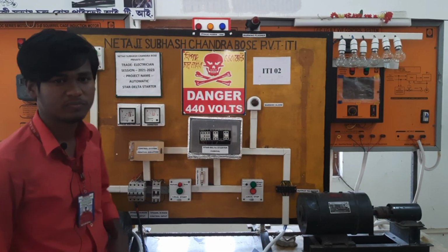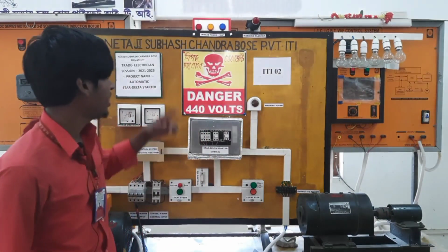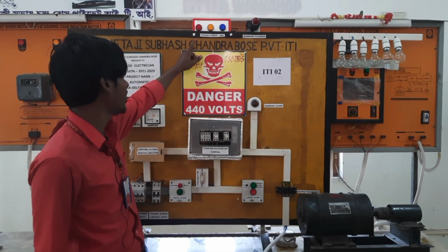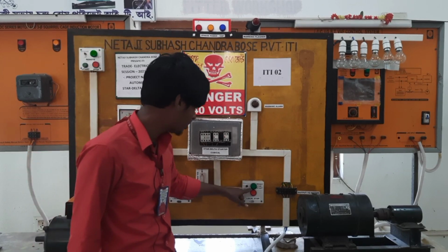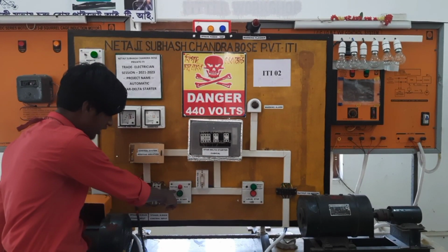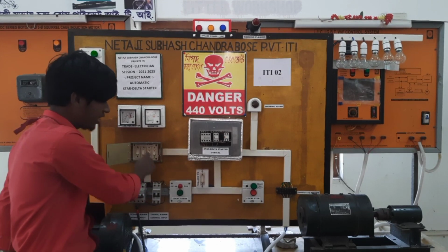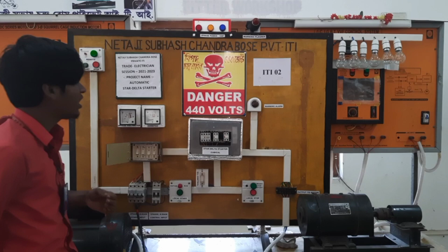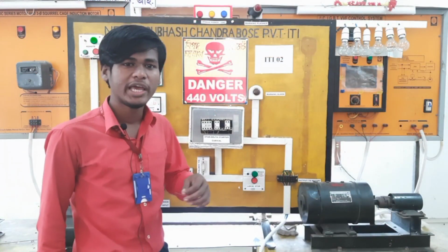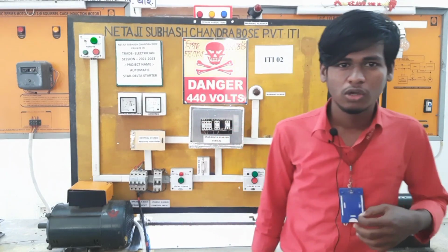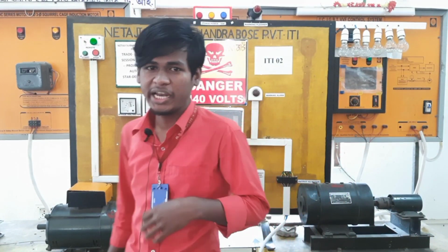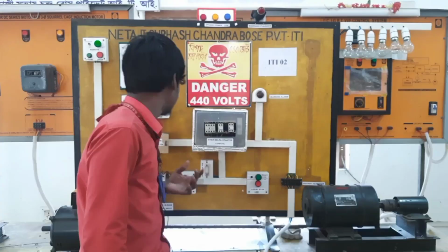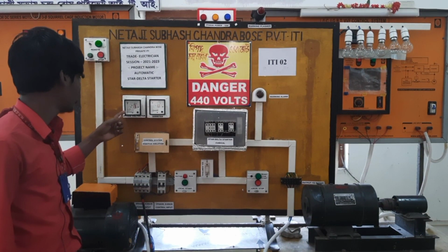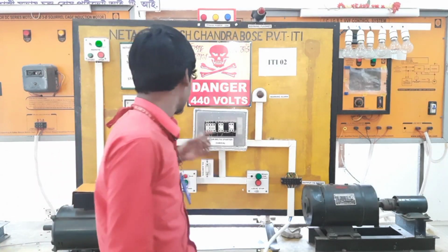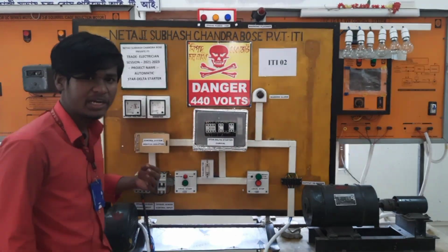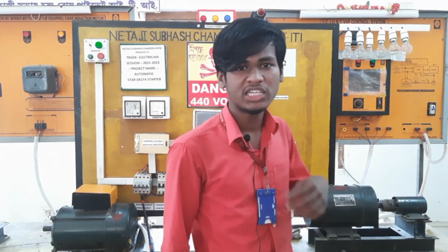Here we have used different types of indication, that is 3-phase power on red, yellow, blue indication, motor is ready for start green indication, motor is in running condition red indication, motor is under maintenance blue indication, and pre-indication before starting with red flasher. For awareness purpose, before starting the motor we have used an audio announcement system and then a hooter with flasher. Different measuring instruments: voltmeter is used to measure supply voltage, and ammeter is used to measure line current when the motor is running in either star or delta position.